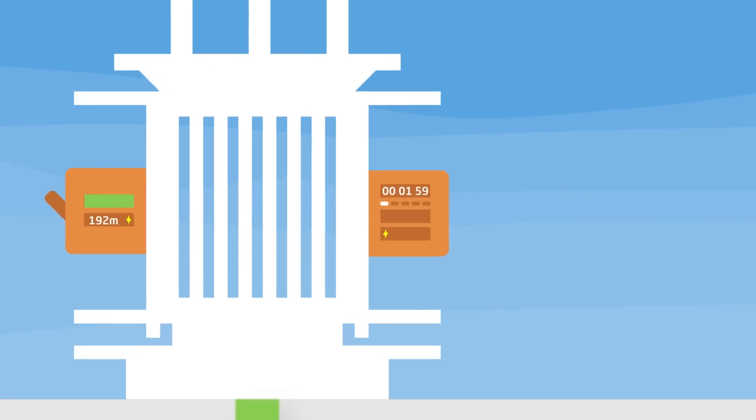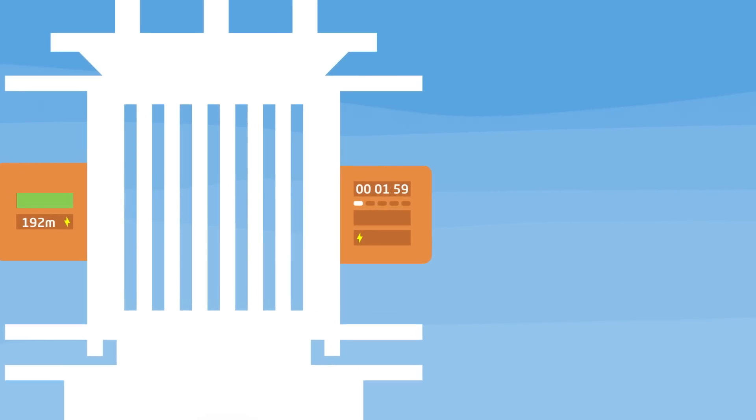We also use special types of fuse that can restore power after just 120 seconds and automatically do this up to five times. It also measures the fault current and provides a distance from the fuse in the substation to the fault to help our engineers locate the fault in the street.